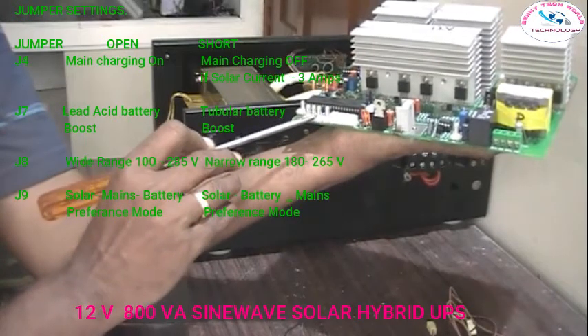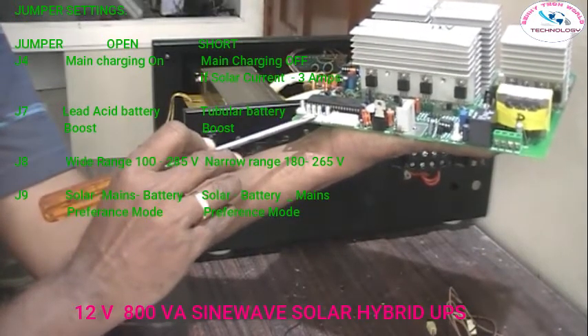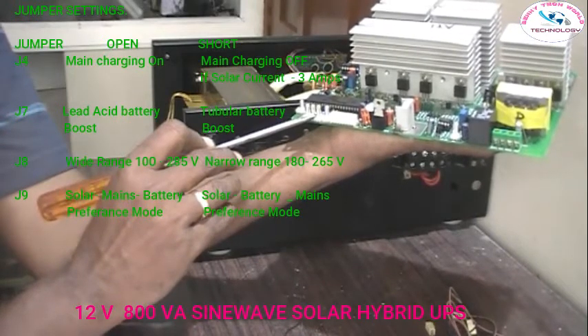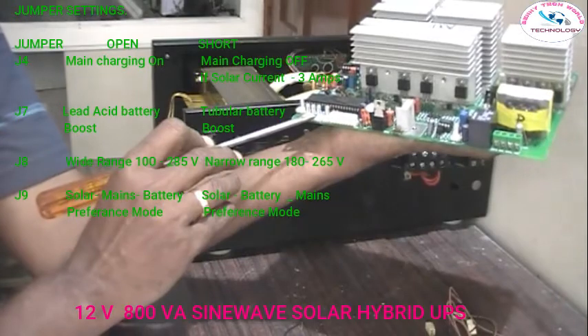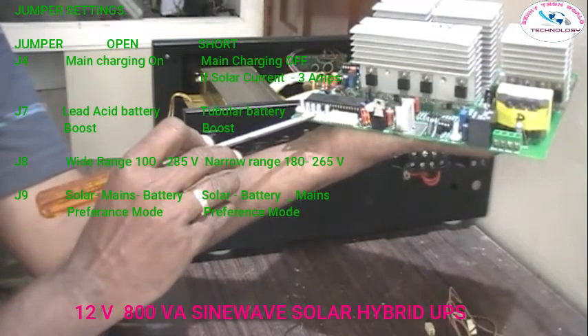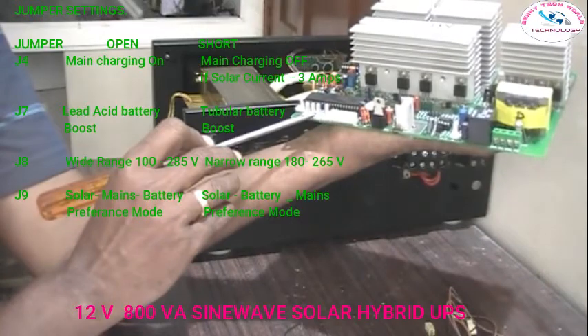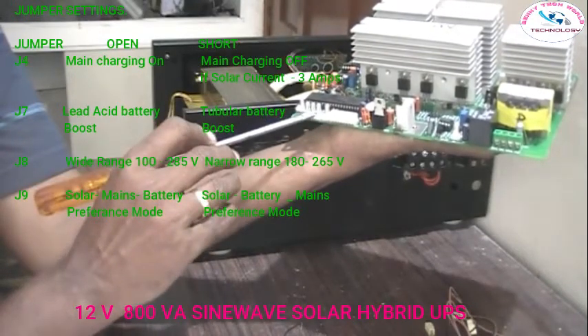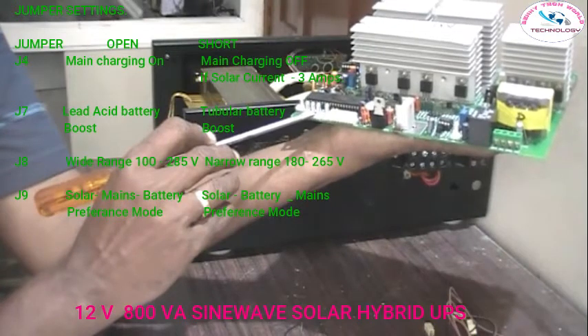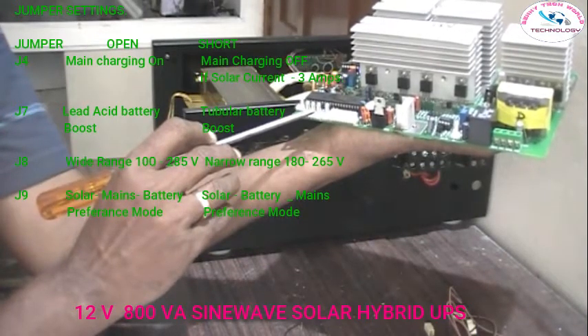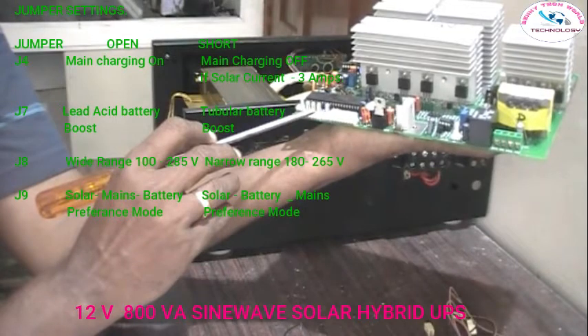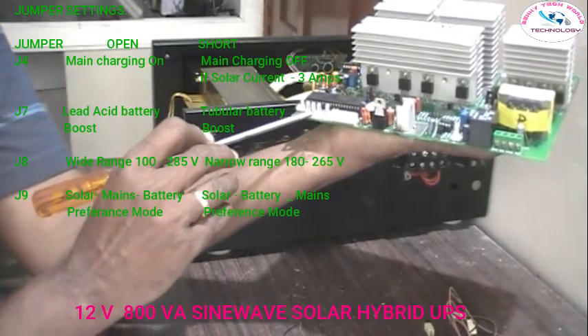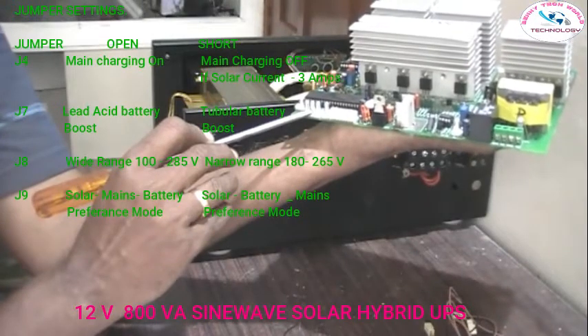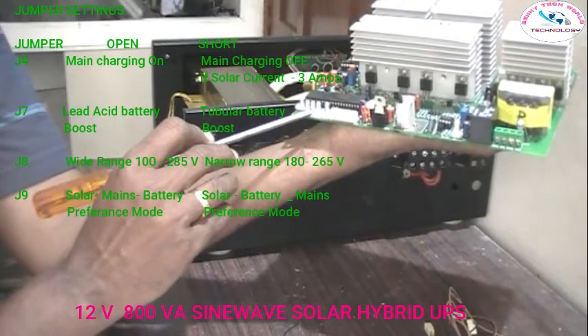The next one is J8, for wide range charging. If in any area the EB supply varies, with input normally 230 or 220 volts, and the voltage varies from 100 to 285, or the input voltage is very low, the switch is off, giving wide range charging from AC 100 volt to AC 285 volt. If the switch is on, narrow range charging is available, with charging control from 180 volt to 265 volt.